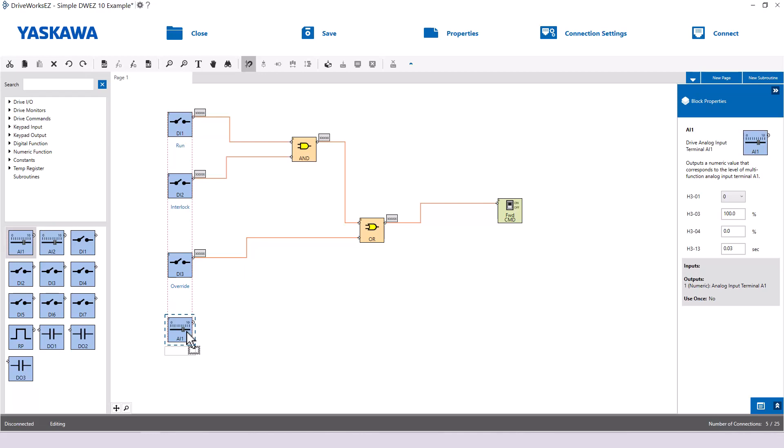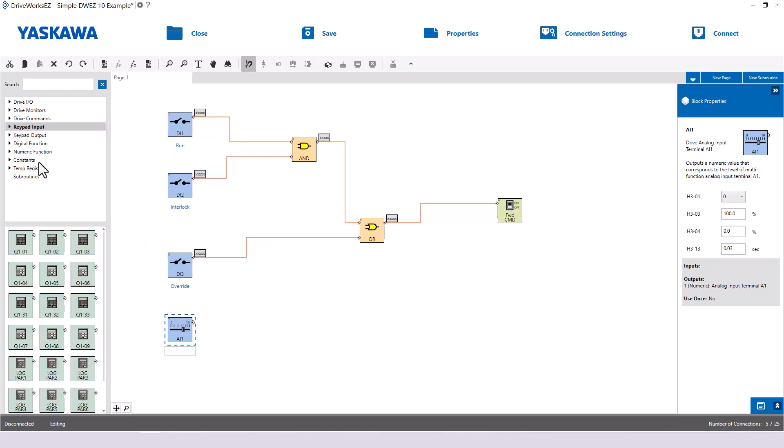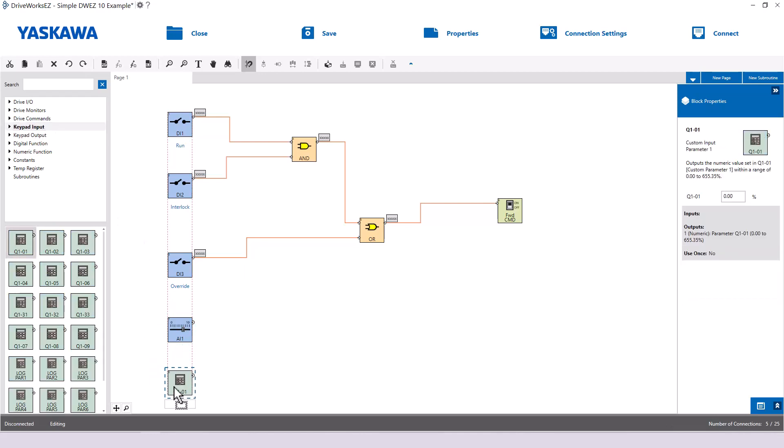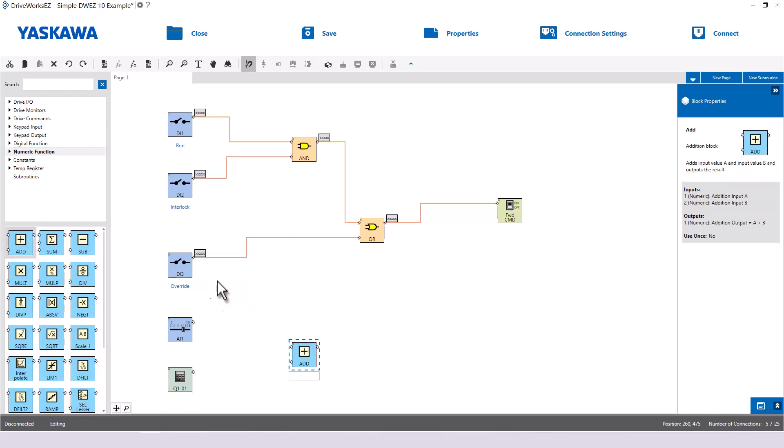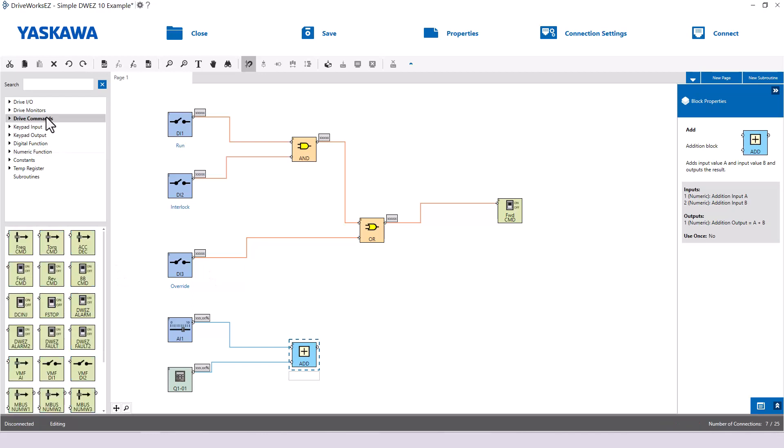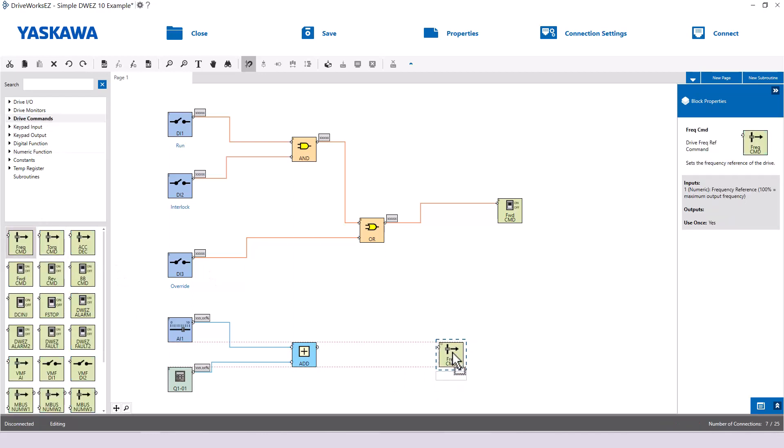With DriveWorks EZ, this can be accomplished with ease. Drag a keypad input block onto the page. Grab an ADD block and connect the analog input and the keypad block both to the ADD block. The output of the ADD block will be connected to the frequency command block.